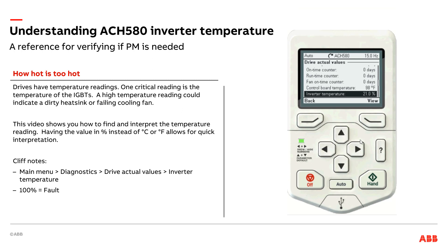Again, 100% equals fault. Usually you're going to get three to 5% below that is when the warning is going to kick in — it depends on the frame size of the drive. So somewhere around 95%, 96%, or 97%, depending on the drive and how it's designed, is when you're going to see a warning threshold kick in.